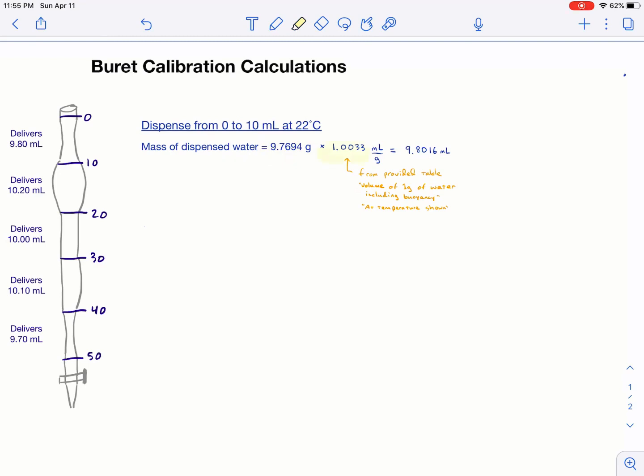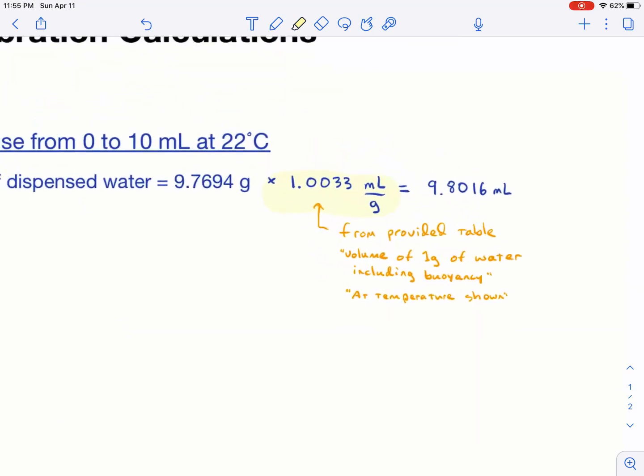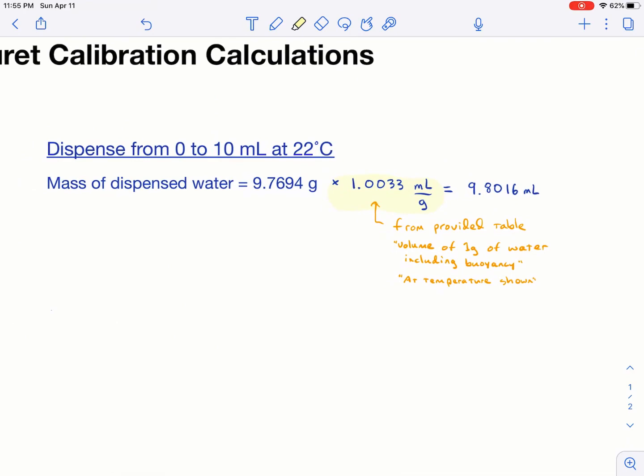And you multiply by the number that we give you that's in the table. And so this provided table has several columns in it. You want the volume of one gram of water that includes buoyancy. So it's an adjustment to the measured mass due to the fact that things float in air. Not very well but they float a little bit. And we don't want the temperature corrected for different expansion and contraction of glass. So we just want the one that says at temperature shown and not converted to a different temperature. So you put that number in. Do keep in mind this number is backwards. It's not density. I shouldn't say it's backwards. It's an inverted density. And so you have milliliters per gram. So all you need to do is just multiply that thing.